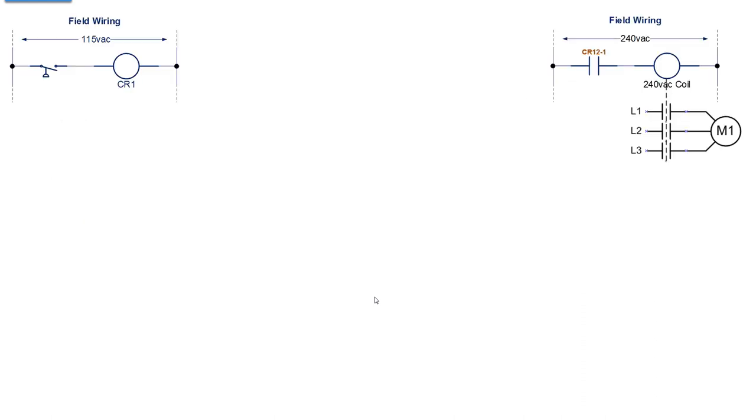Let's take another example. Here's our field wiring. We have a pressure switch. That pressure switch operates on 115 volts AC in the field, it energizes a contact relay CR1. On the output side we have field wiring, we have 240 volts AC. Somewhere there's a relay CR12 that will control this contact, and when this contact closes it will energize that coil, and will close three contacts that supply three-phase power to the motor.